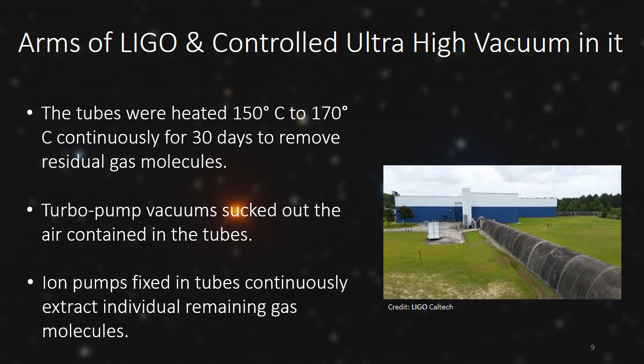Now we want to create vacuum inside these tubes. That's why turbopumps were used. These turbopumps sucked out the air contained in the tubes. To create vacuum is one part, and to maintain such vacuum is another. So ion pumps were installed in these tubes. These ion pumps continuously extract individual remaining gas molecules from the tubes and throw them out.